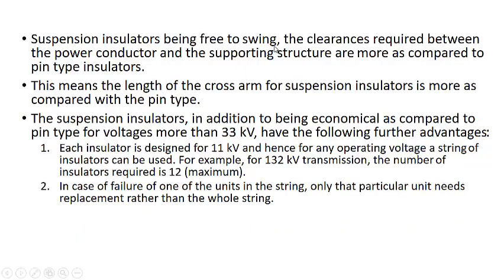Suspension insulators being free to swing, the clearance between the power conductor and the supporting structure is more as compared to pin type insulators. This we can say is a disadvantage, because they are free to swing along with the conductor. So the clearance between the conductors should be slightly greater as compared to conductors using pin type insulators, because pin type insulators are fixed and not free to move with the conductors due to wind. This means that the length of the cross arm of a suspension insulator is more as compared to the pin type insulator.